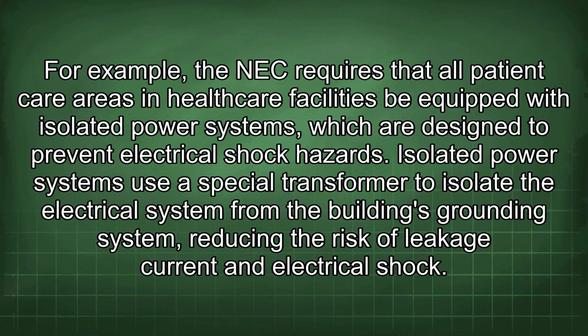For example, the NEC requires that all patient care areas in healthcare facilities be equipped with isolated power systems, which are designed to prevent electrical shock hazards. Isolated power systems use a special transformer to isolate the electrical system from the building's grounding system, reducing the risk of leakage current and electrical shock.